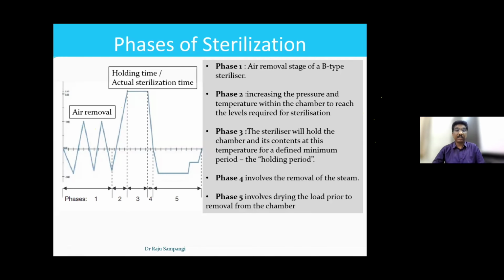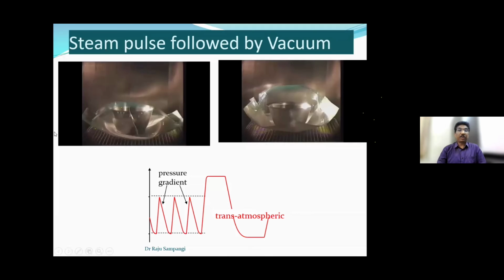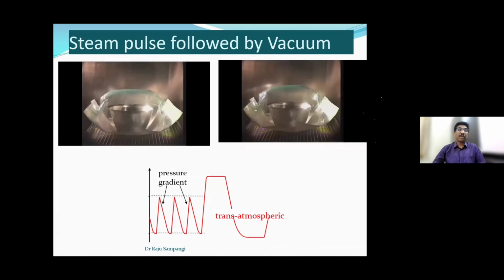So these are the phases, and it's important to understand all these phases, because depending on the load, you have to alter some of these phases. So coming to the pulsed vacuum I was showing you. Here you can see the steam being injected. You can see how this wrapped item is expanding, how the packaging is getting expanded when we are injecting the steam into the sterilizer.